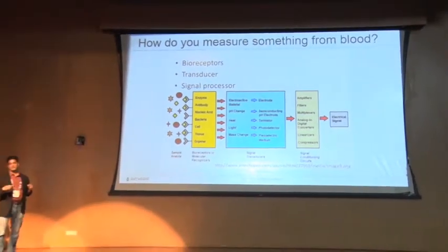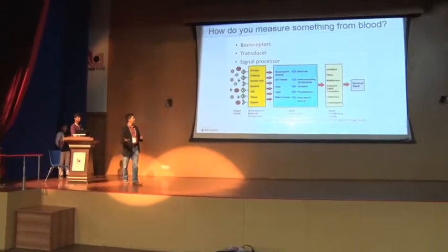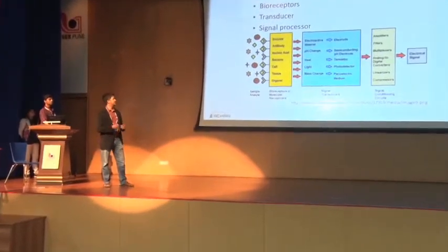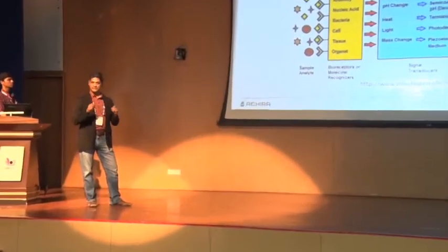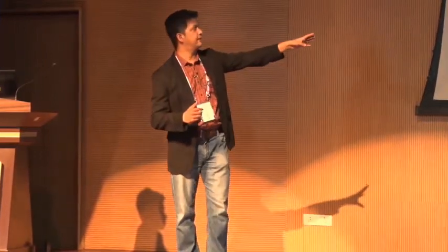And by that action, it sets off a series of reactions which, in the most common case of glucose sensors, is actually sitting on an electrode. You have some electroactive materials there, and that finally generates a current. That's the entire signal transduction part. And then that goes to some signal conditioning circuitry, some electronics, and that gets spit out finally as your glucose value. So pretty much every diagnostic test that's done has something within here.